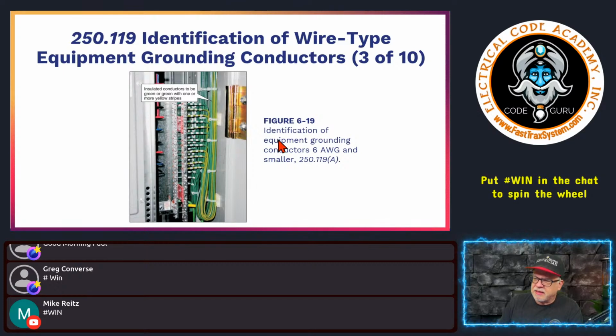Identification of the wire type. Here you see insulated conductors in green or green with one or more yellow stripes. I'm just assuming this piece of equipment has a bunch of isolated grounds as well or something like that. I don't know the equipment, but this is just showing you. One of the questions I get from people who look at images like this, and they see this bend right here, is: isn't that exceeding the minimum bending radius of a single insulated conductor?